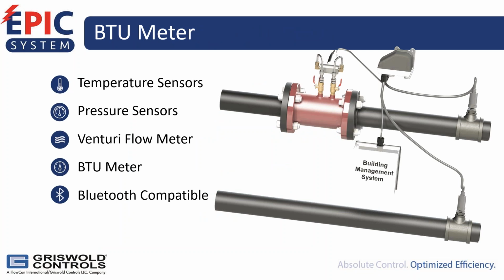And within the EPIC product line, we have the BTU meter. The BTU meter has a Venturi metering station to measure flow. It also has differential pressure transducers and 2 temperature transducers so that we can measure the BTU. The data is provided directly to the building management system, or it can be viewed on any phone app. BTU meters are used in applications where a building owner wants to monitor or even perhaps charge the tenants for energy. Our metering stations have been used for years for that application, but now the phone apps actually calculate the BTU because we are capturing the delta T across the heat transfer equipment. They can also use that temperature data from sensors to calculate the BTU in their building management system.